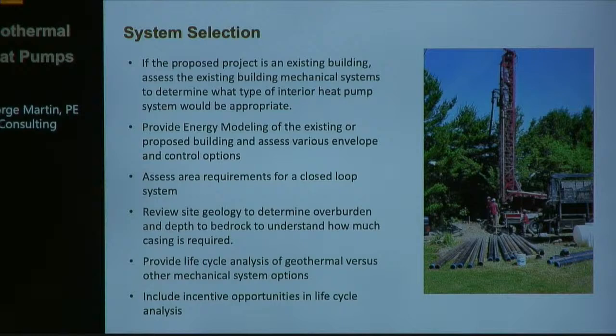We assess the area requirement. This site has plenty of area, so at a high level there should be no issue with the geothermal system fitting on site. We do like to review the site geology, which is what we do with the test well - that helps understand how much casing is required, basically the amount of soil before you hit bedrock, and then if there's water. I do know there's water around the area, so there's actually a lot of water within the site based on wells in the area.